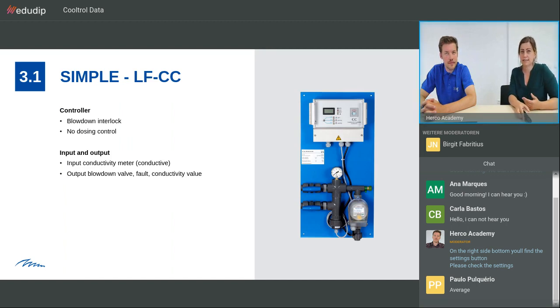Okay, LFCC, that's the simple one. That's historically speaking because, first of all, the first blowdown controllers, not just from us, but in general in the industry, were mainly concerned with the main function. That means the blowdown interlock. Okay, when can I start the blowdown? When the conductivity is over a certain set point. But there was no dosing control. That means this control of the two different dosing systems, volume and time proportional, is not included yet. So this is the most basic version. But if there's a simple cooling system, it can still be the most adequate version.